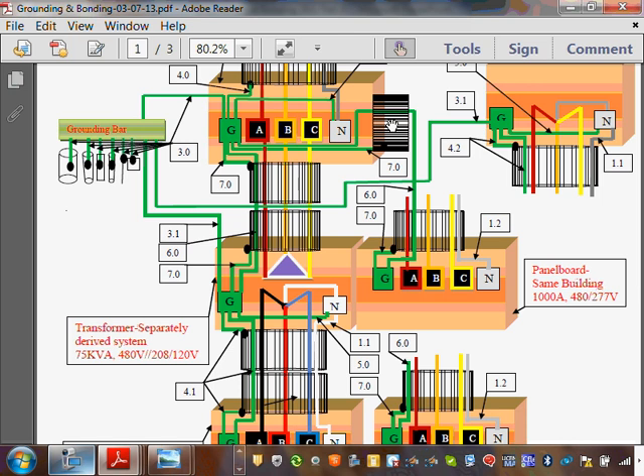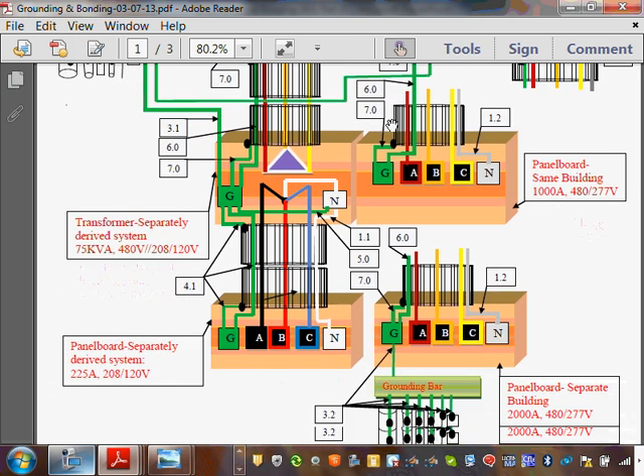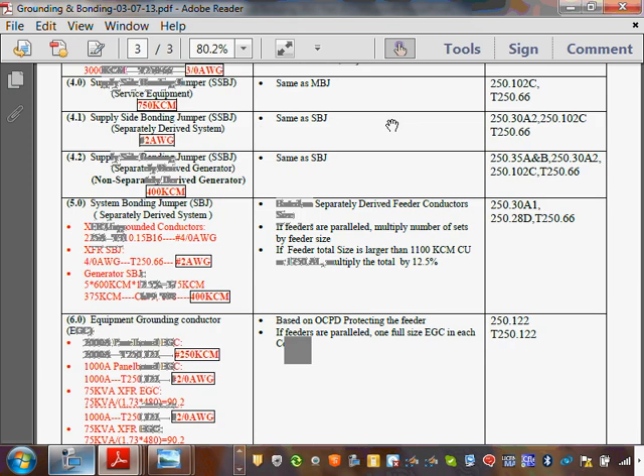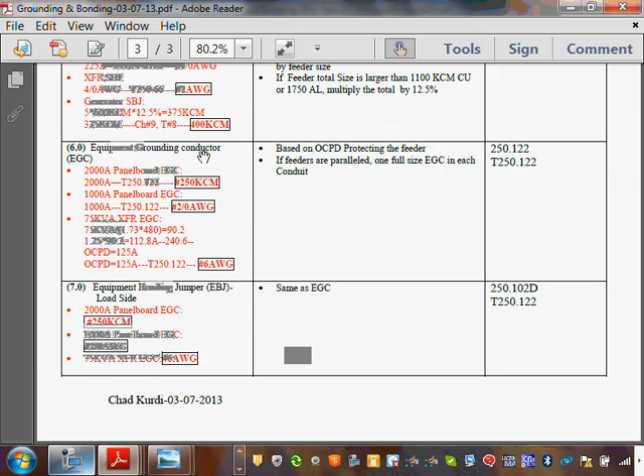So now we're bonding with the conduit. Let's go, guys, to 6.0 and 7, all the way to the bottom. Okay, equipment grounding conductor, that's what the NEC code book calls it, EGC. How do you size it? Here's my reference, table 250.122. You size it based on the overcurrent device. And if feeders are paralleled, one full-size equipment grounding conductor in each conduit. This is very important. If you're paralleling, you have to put full size. You don't cut it by the number of parallel sets. Full size in each one of them.